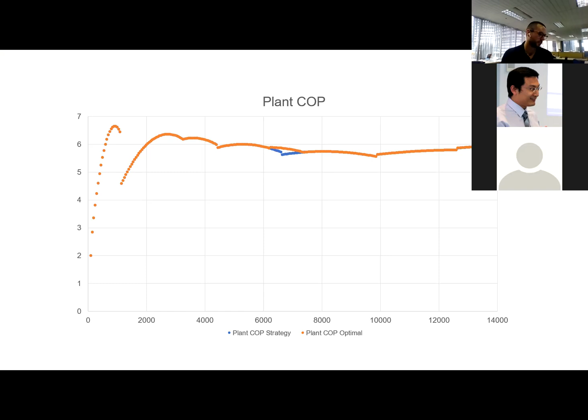But we actually went through, so all of these strategies, after they're popped out from the model, we will go and review and look at things like chiller runtime. And if this was the case, the runtime of that low load chiller would actually start to take off and really outpace the high load chillers. And then you've got all sorts of problems with replacing one bit of plant before everything else is ready to be replaced. So given that it was only a small difference in COP, and it turned out to be, I think, less than 0.5% potential energy savings, it was judged that rather than do that, let's just run the high loads at high loads and not bring this low load back on again.